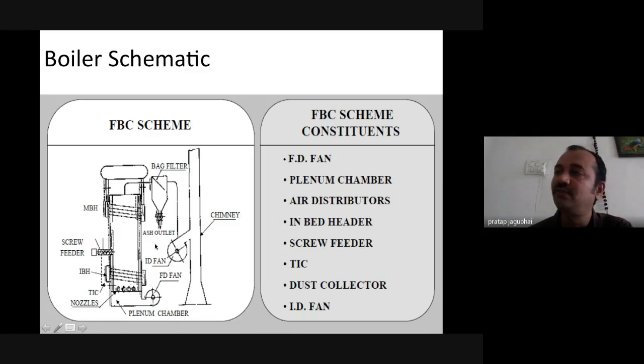This is a typical solid fuel boiler, consisting of the draft in the form of ID fan and FD fan, fuel delivery through the screw feeder, which means it is a solid fuel boiler, and the steam drum and water wall membrane with the main bank header, with the emission control equipment. Whichever flue gas is coming out from the furnace should be cleaned enough before leaving through the chimney to the atmosphere. That is the emission equipment. So bag filters or electrostatic precipitators are available for emission control, and this will complete the construction of the boiler.